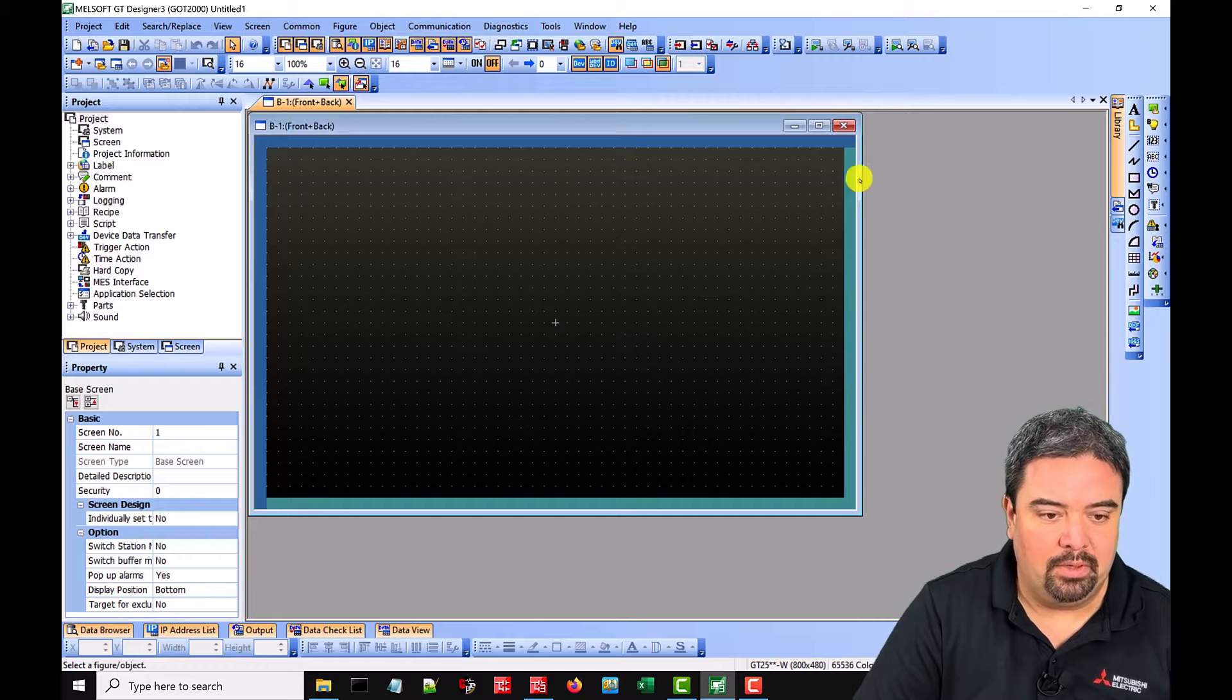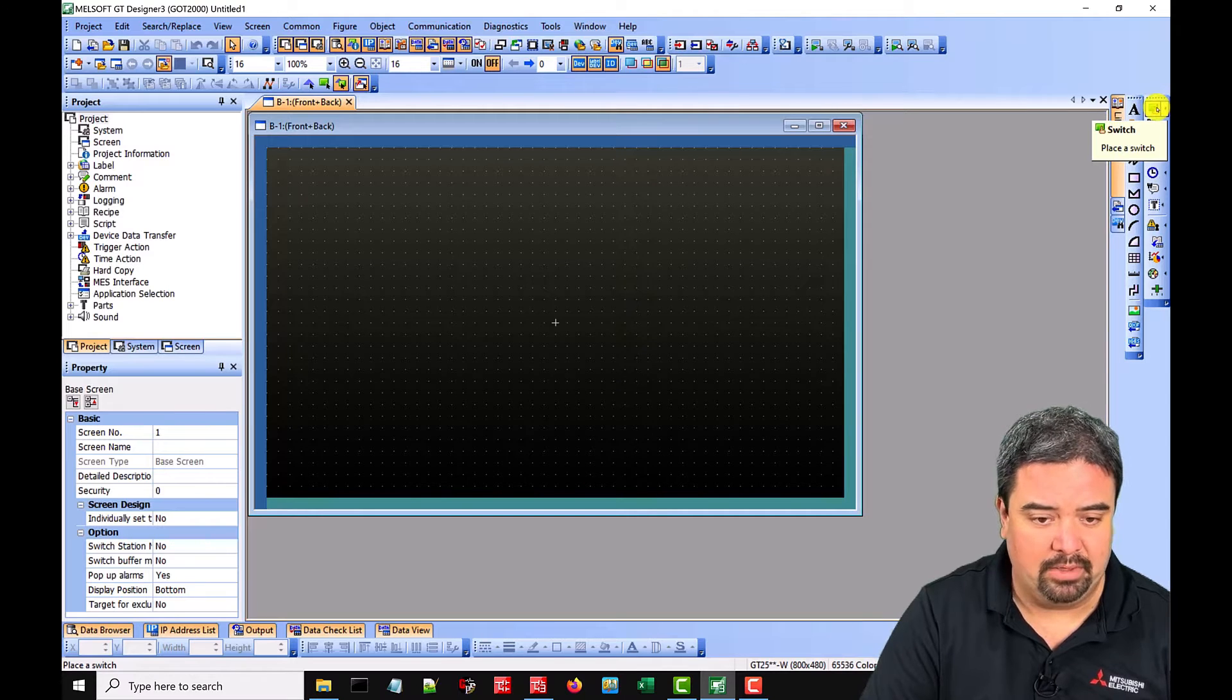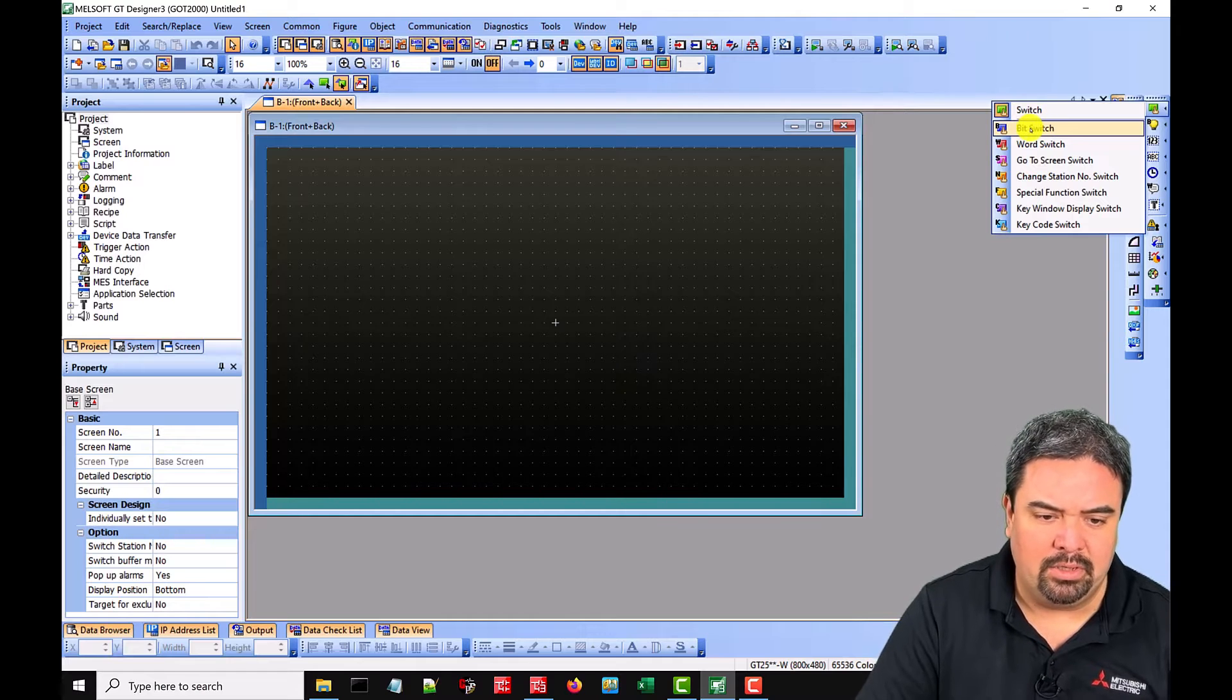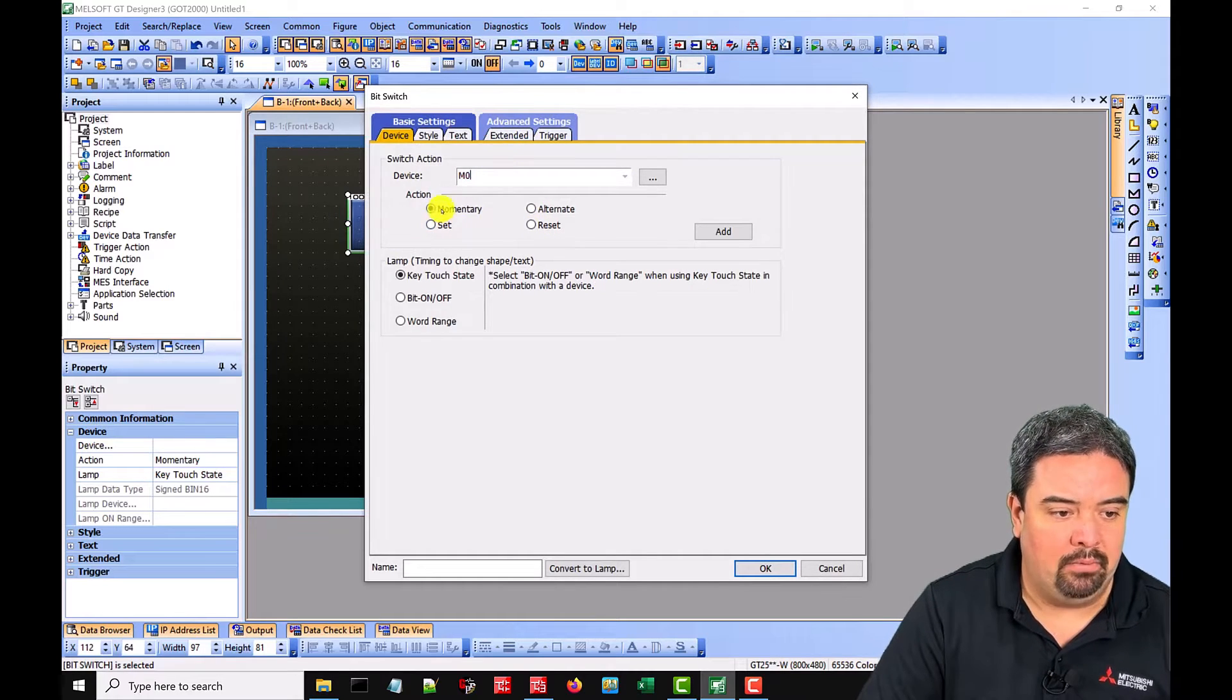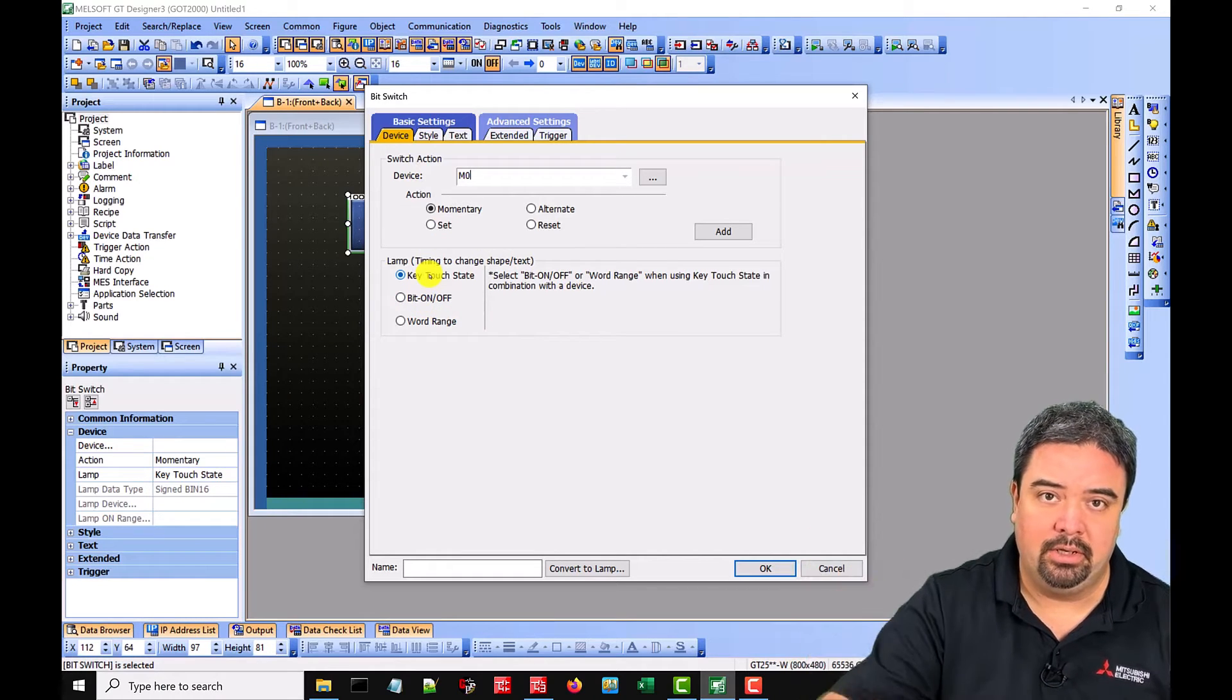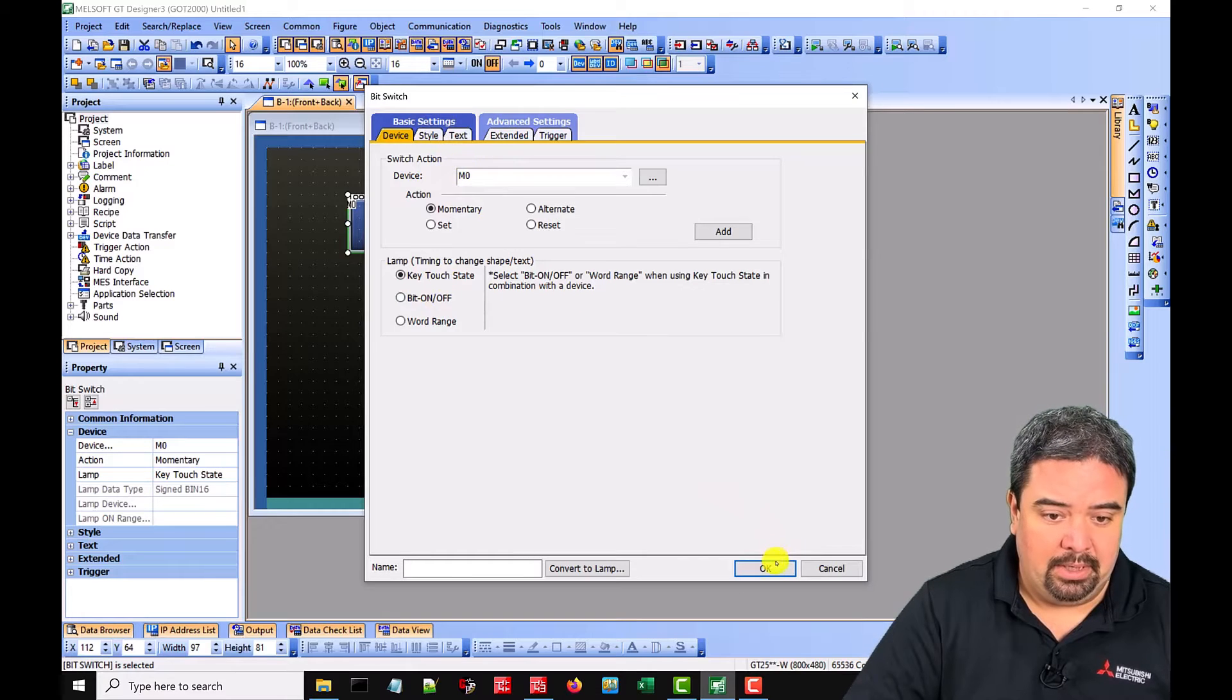Over here we have a switch block. If we just do generic that will give us any type. If we know exactly what we want, in this case we're going to do a bit switch, we can select it. If we did the generic we can choose what we want later on. But we're just going to do a bit switch and then bring this into our project. Double click, we'll call this M0 and we'll just make this a momentary, so just as long as we're holding it. We could also do a set and a reset or we could do an alternate. We could also choose how we want the lamp to be shown. In this case we're just going to make the lamp trigger if we touch it. But we could also say if M0 is on make it lamp out of that. So that's our M0.